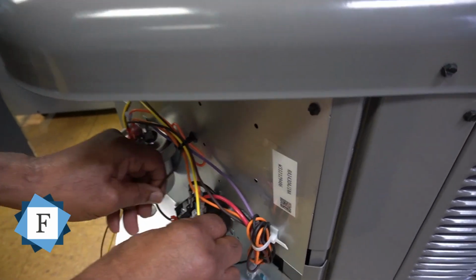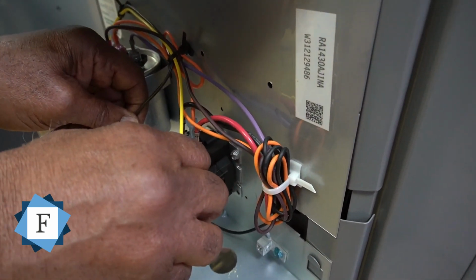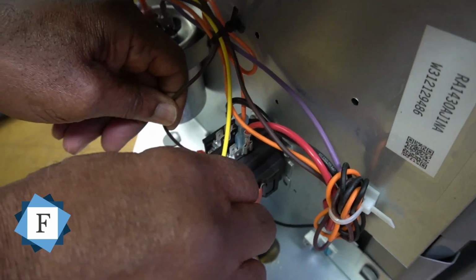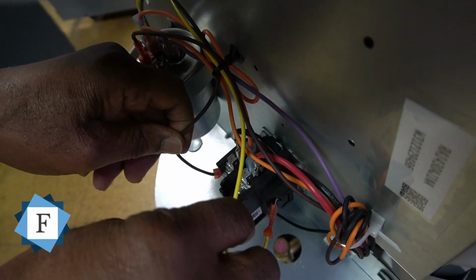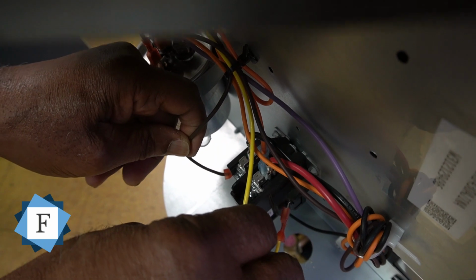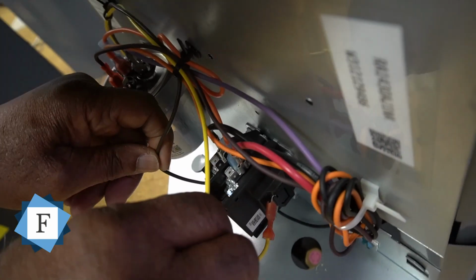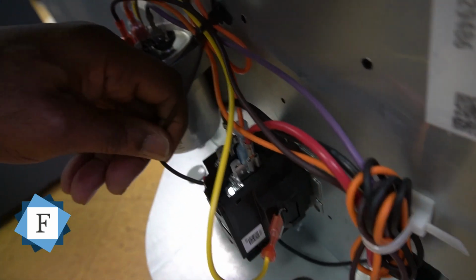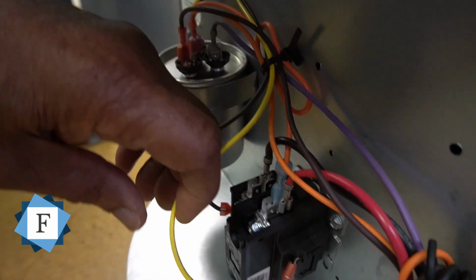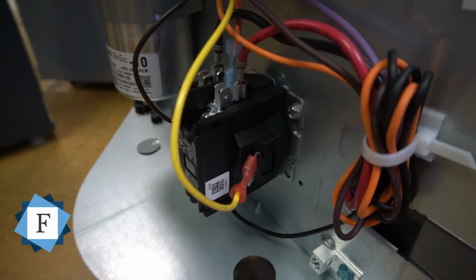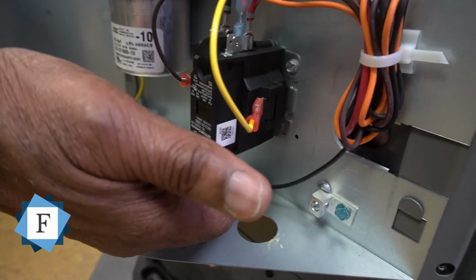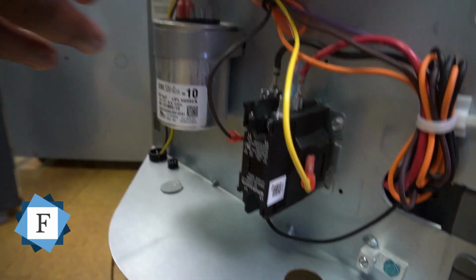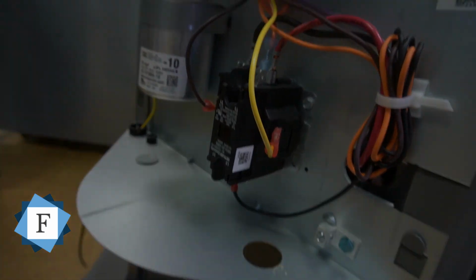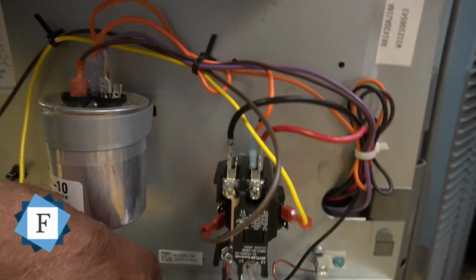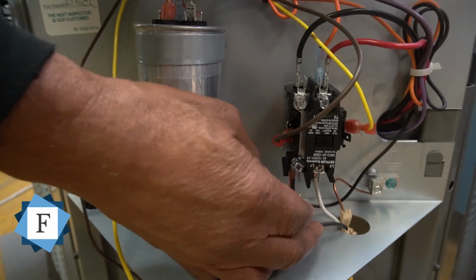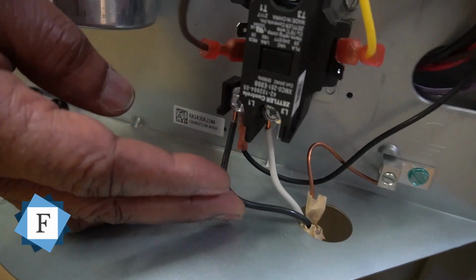It has to be made at the contactor. This is the 24 volt side of the contactor. 24 volts coming from inside your house, the furnace, on the low voltage side of the control board inside your house, and we'll point to that as well. The low voltage sides of your furnace, 24 volts. And this is 240 volts coming in at the bottom. 240 volts here coming in from our outdoor disconnect.